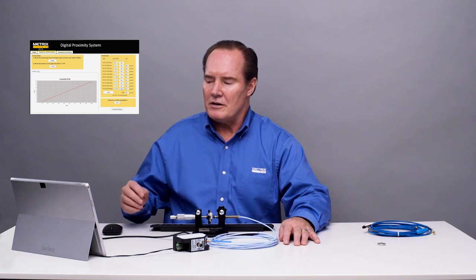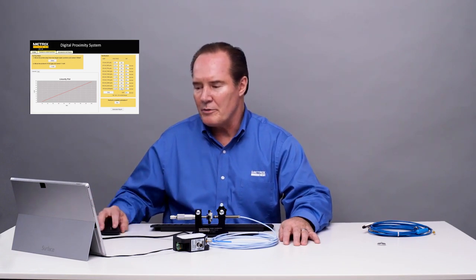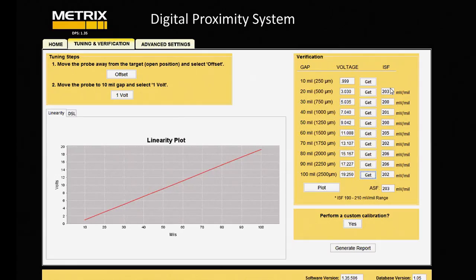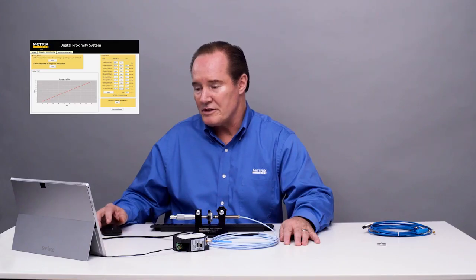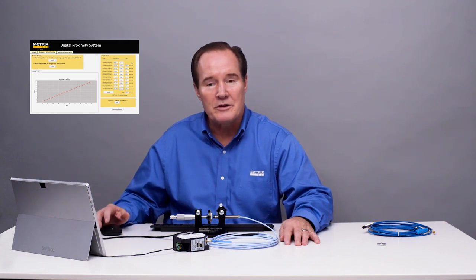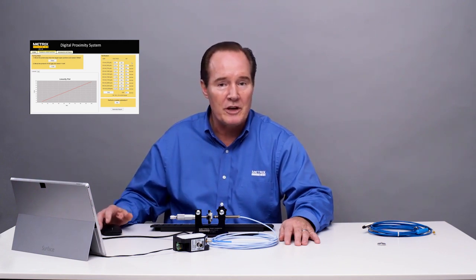All right, that was our last point, and if you look at the incremental scale factor, it's between 190 and 210 millivolts per mil, and that's really excellent for a proximity probe system, and it shows that the Metrix digital proximity system works with a competitive probe and cable. Thank you very much.